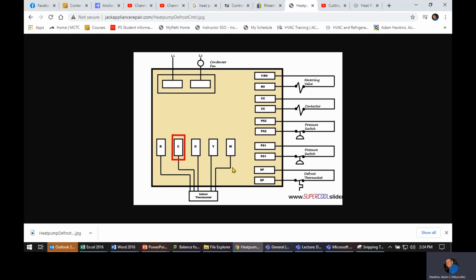So you've got a white wire that's coming back from the stat, or back from the board, calling for the emergency heat strip to come on. The thermostat doesn't call for those. The board does. The board does what the stat would do, basically. It bypasses the stat. So when this thing goes into defrost, a few things are going to happen. So I want you to write these down. There are some variations to this as well, depending on brand, but this is kind of the basic overall.